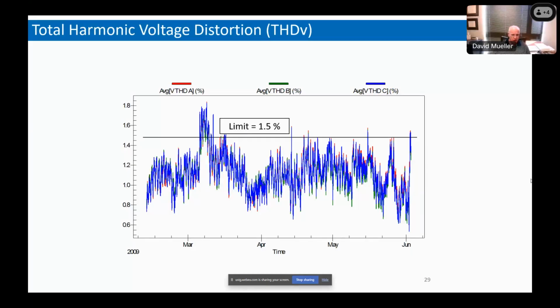And so this is a pretty typical example here. This is actually a site where if you look at the THD and you recognize that the limit is 1.5%, it might look like we're not okay there because we're over the limit. But actually we only need to meet it most of the time, not all the time. We need to meet it 95% of the time. And it turns out that the 95th cumulative probability value of this data was 1.45. So 95% of our measured values were 1.45 and below. So we could actually state statistically that we meet this limit for THD at this site.